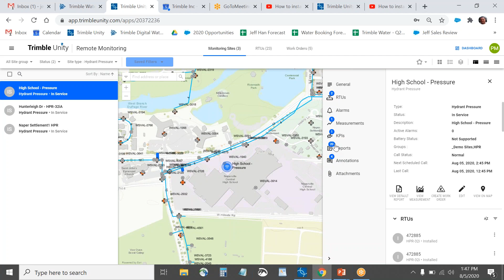If I want to change how it behaves, how it records data, how often it calls in, and set alarming conditions, I can do that from my office without going to the field, by hitting the edit button. Right now it's set to call every day at 1 a.m., but I could set it to call every hour, every two hours, or whatever interval I like.